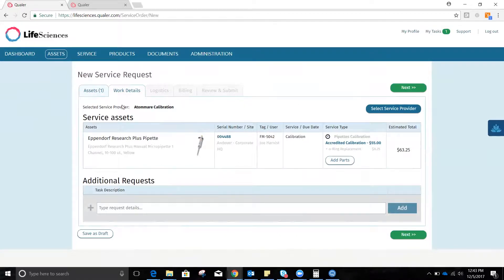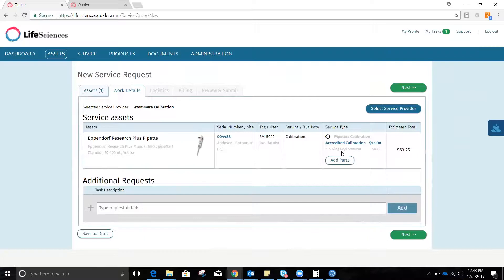It already knows this is going to be an Atomare Calibration. We're going to get the accredited calibration for $55 per our quote and agreement that we have in place with them. We're always going to ask that the O-ring be replaced for every service event done with them, and that's going to estimate the total.